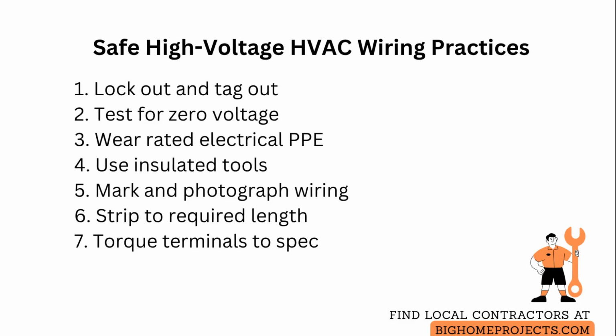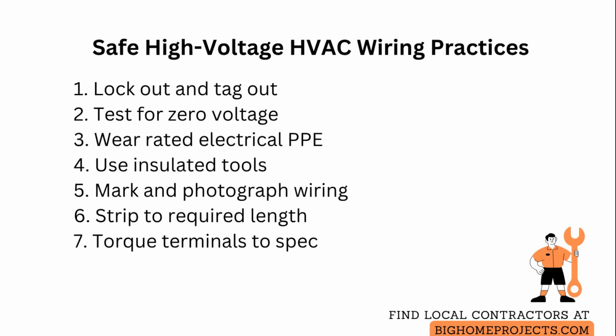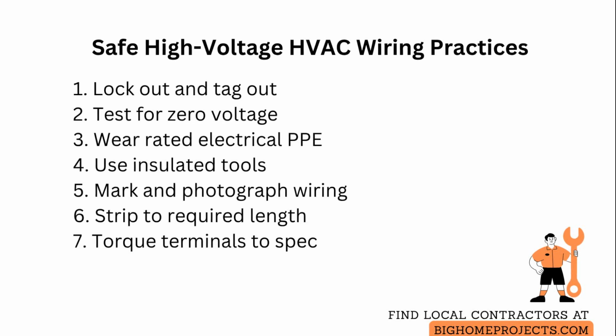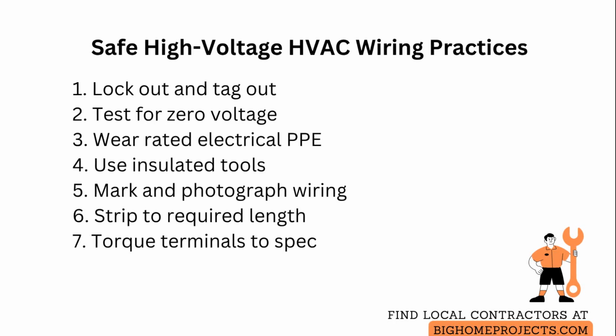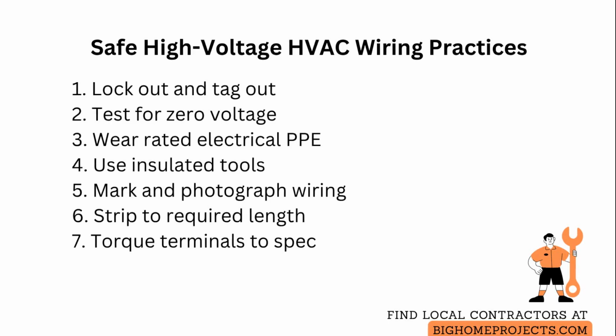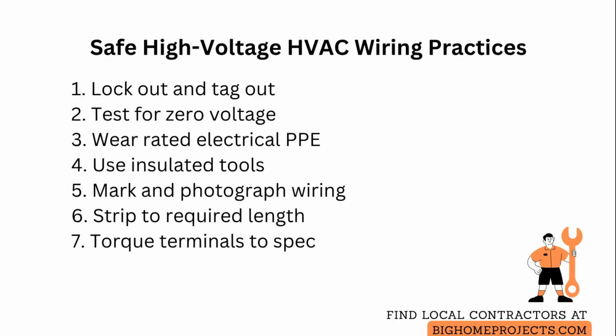Wear properly rated personal protective equipment, including electrical gloves and safety glasses, and use insulated tools rated for the system voltage, so a slip does not create a short. When removing wires, note or photograph their routing and terminal positions and mark each conductor so reconnection is exact. Keep removed fasteners and small parts in a labeled container.